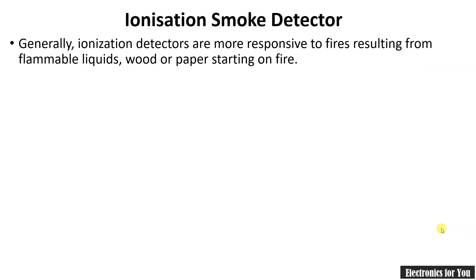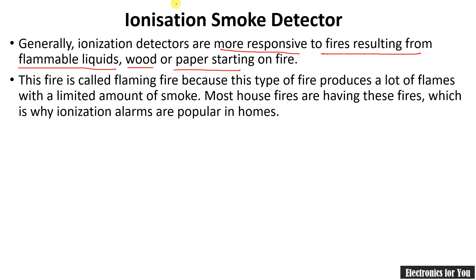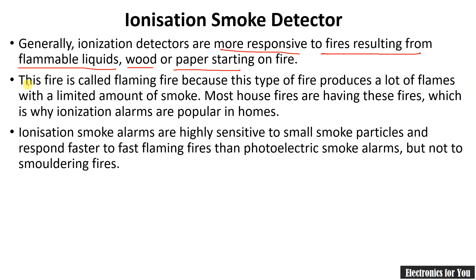Now let's start with the first type: the ionization smoke detector. Ionization smoke detectors are more responsive to fires resulting from flammable liquids, wood, or paper. Since these materials are commonly found in homes, ionization smoke detectors are preferred for home use. They are highly sensitive to small smoke particles and respond faster to fast flaming fires than photoelectric smoke alarms, but not to smoldering fires.